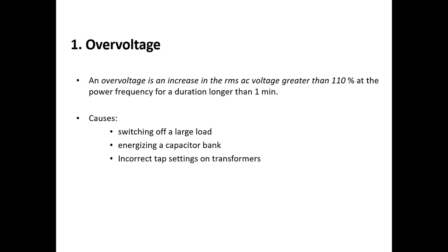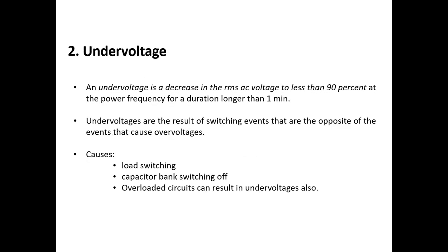Now the next thing that we are going to discuss is over voltages. An over voltage is an increase in the RMS AC voltage greater than 110% at the power frequency for a duration longer than 1 minute. What are the causes of over voltages? Switching off a large load, energizing a capacitor bank, and incorrect tap setting of the transformer. In that case you will get over voltages.